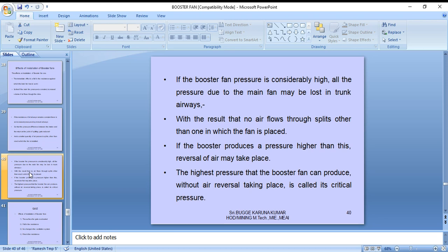booster fan is concerned. The booster fans are largely underground fans that can increase the volumetric efficiency of the ventilation system by balancing the pressures and quantity distribution throughout the mine, reducing leakage and reducing the total power requirement. Booster fans are prohibited in underground coal mines in the United States. That is very important. Some countries prohibit them due to recirculation of air or efficient such plants.